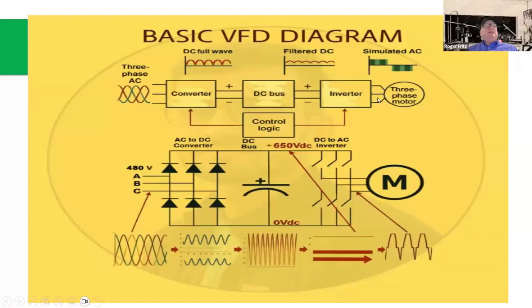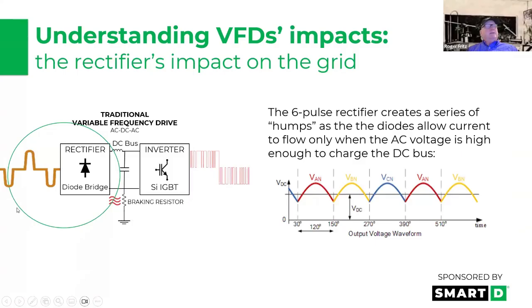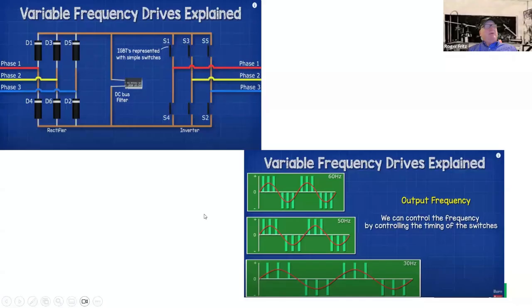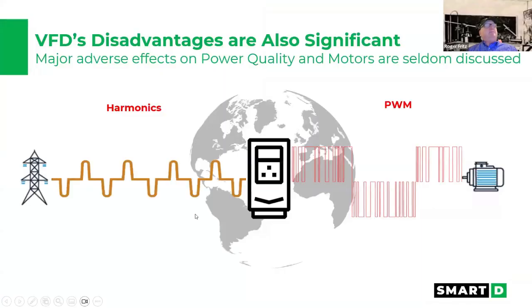When the cables are relatively short, and you've got grounding rings in the motor and spike resistant wire in the motor, they work relatively well, and that's again 90 to 95% of the VFDs in the marketplace. So you see here where it rectifies, creates this bumpy waveform, and then they use capacitors to smooth it out, and then they control the PWM from 60 cycle. They'll spread it out to 50 cycle or 30 cycle, and you can go from 0 to 60, and you can even go up in frequency with a variable frequency drive.